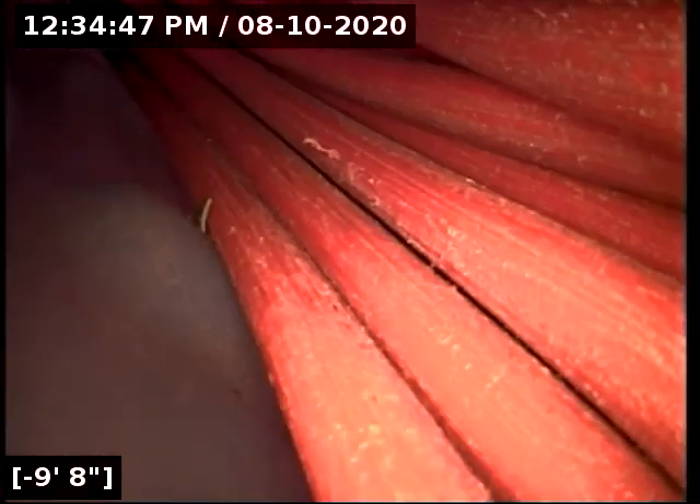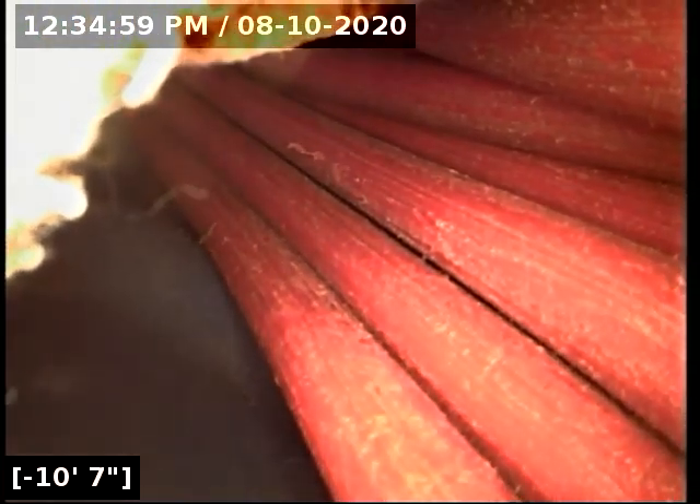Cleaning it will improve the flow of the sewer line and give you a proper view of the bottom of the pipe to make sure you don't have rotted sewer pipe there. The line is still functioning, don't get me wrong. Sometimes you can get junk underneath all that. As we get back into here, you can see how the pipe opens up a lot more — you don't have all that black sludge in the flow line. We do have adequate flow to the main lateral connection. The PVC pipe is in good condition. The cast iron appears to be in fair to good condition. Unfortunately, I can't see the entirety of it with buildup in the flow line — most of the cast iron has that in it, probably about three quarters of it. I would recommend removing the buildup and re-scoping to check the work and to ensure that the bottom of the pipe is still in good condition. The line is functioning at this time — it's draining a little slower than I'd like due to the buildup, but it is functioning. If nothing is done, I would certainly re-scope the line in time or get it cleaned out at some point. Make sure you take a look at that pipe bottom.